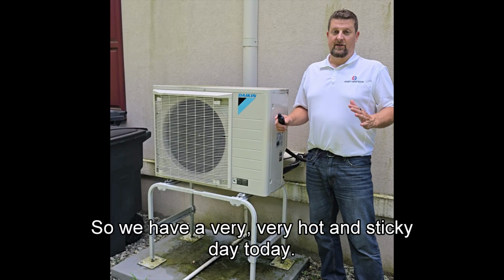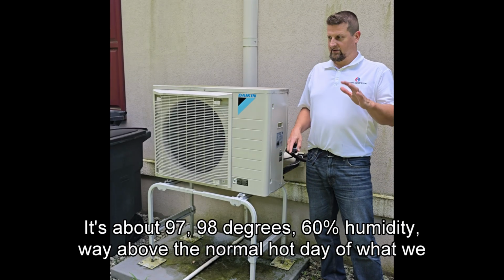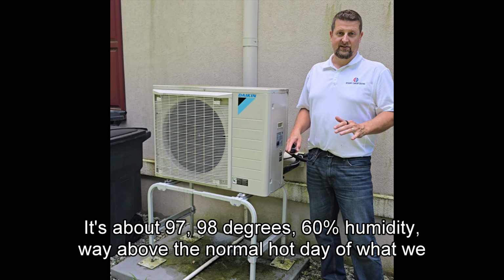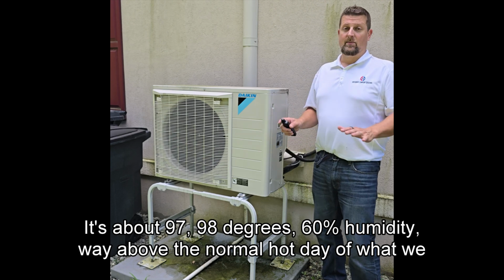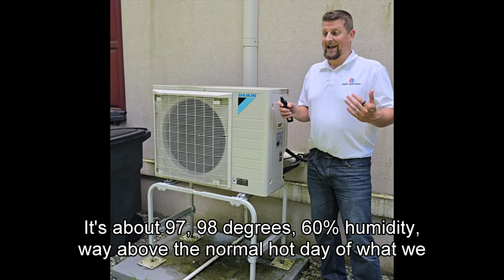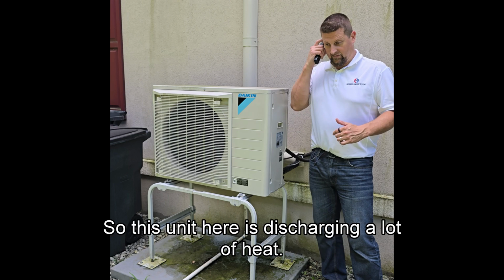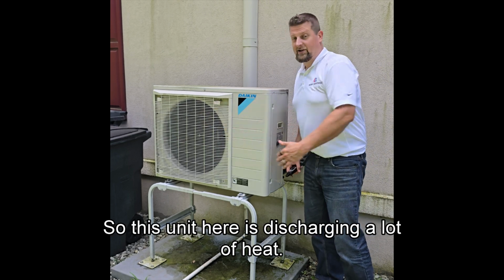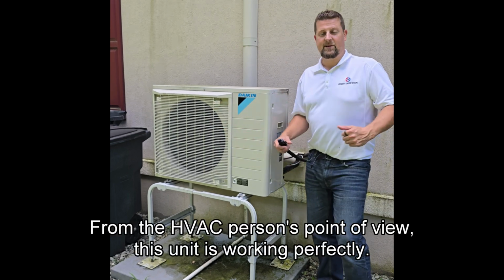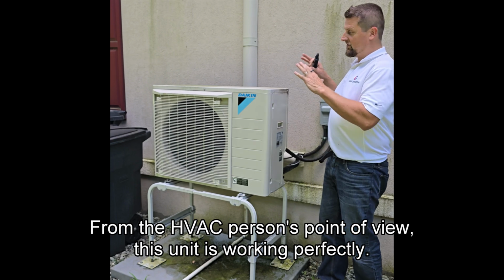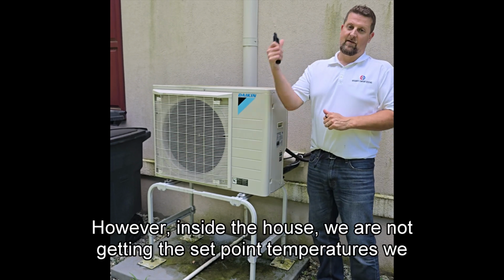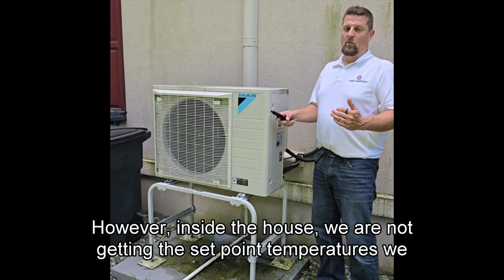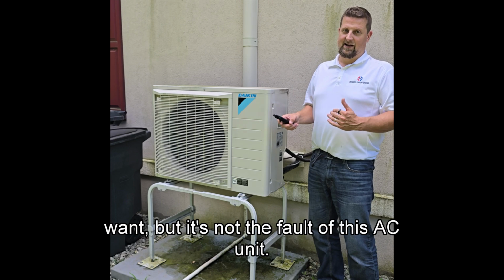So we have a very, very hot and sticky day today. It's about 97, 98 degrees, 60% humidity, way above the normal hot day of what we experience around here. So this unit here is discharging a lot of heat. It's working. From the HVAC person's point of view, this unit is working perfectly.